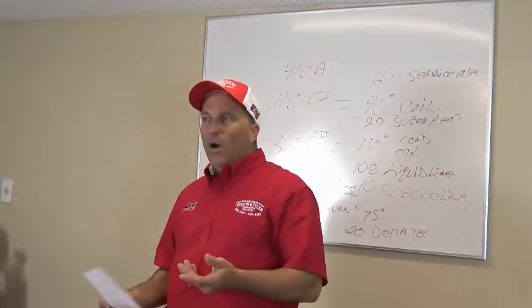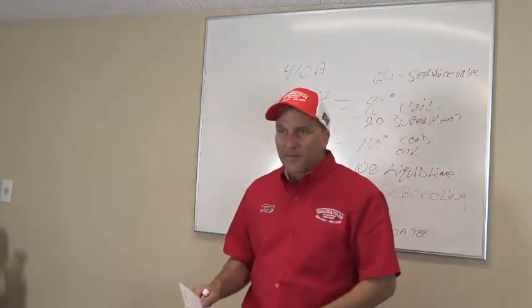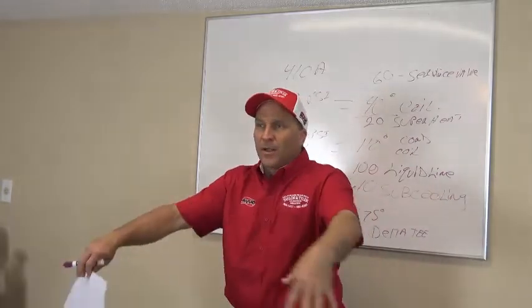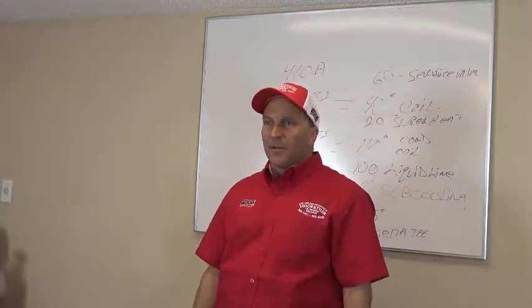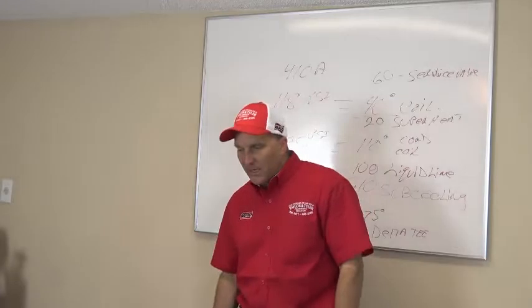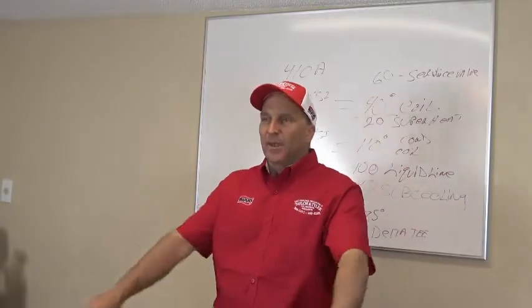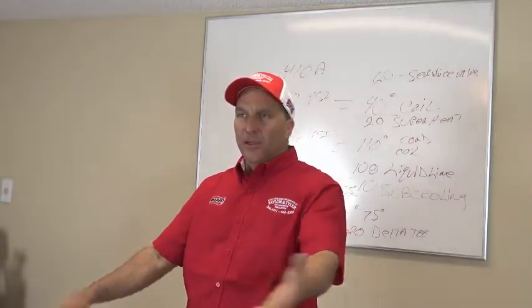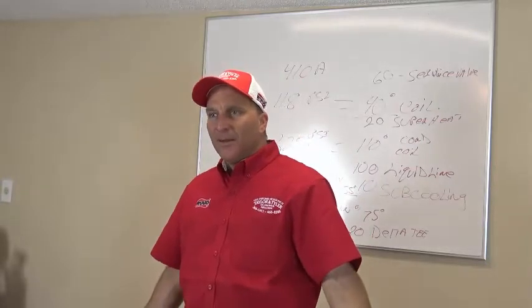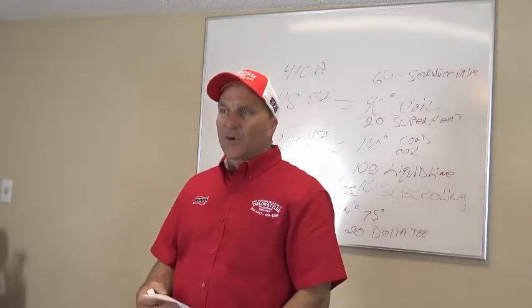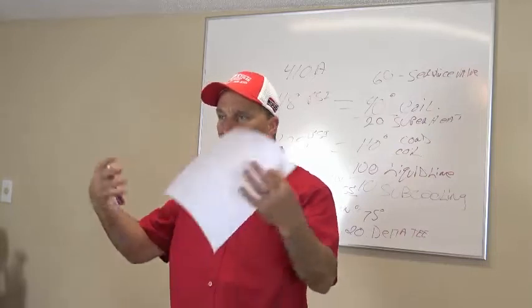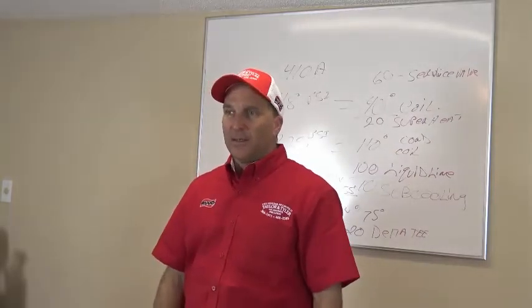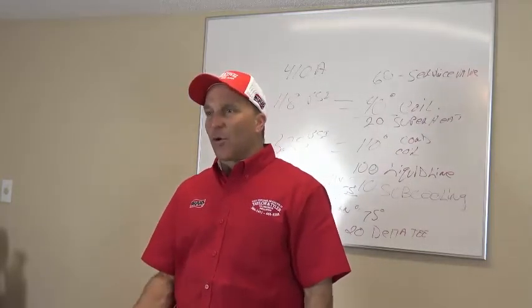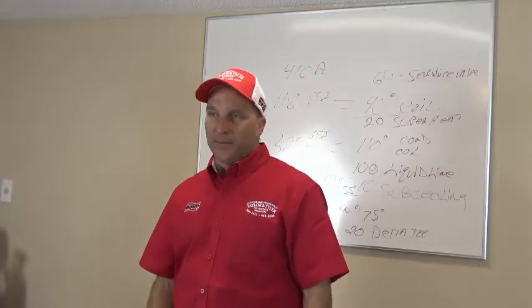You can't always see that the condenser coils are dirty. How many times do you walk up to a Goodman unit, look at it, you can see the fins around it, it rains on it all the time, and you go, that's not dirty? It's on a clean piece of cement. Does it look dirty? Spray it, it shows. Once you spray the chemical on it, it turns brown and gray and black coming off of it. So every condenser coil, I'm telling you, is dirty.